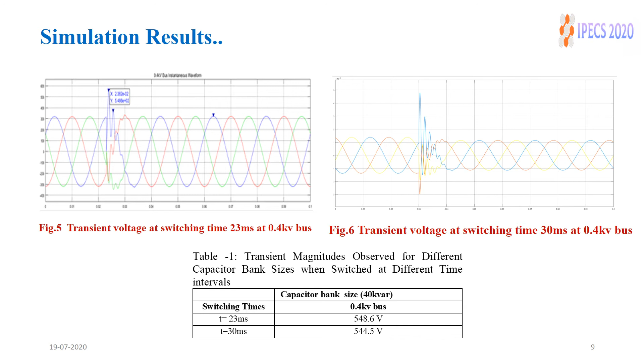So what is the conclusion of this study? Actually, when we increase the switching time, we get very low peak voltages. When we decrease the switching time, in the opposite way, we get higher peak voltages. So it's very important when you do shunt capacitor switching for power factor improvement that you take care about the switching time. If you fix the switching time at a proper value as per the standard value, then you get the peak voltage within the limit. It does not harm or damage the sensitive protective equipment in the power system. So this is our conclusion from this research.